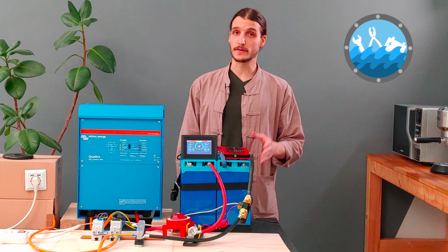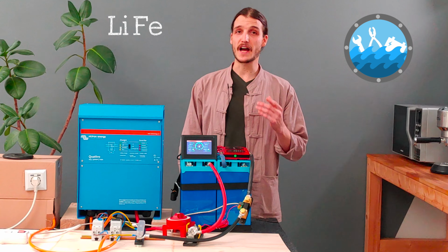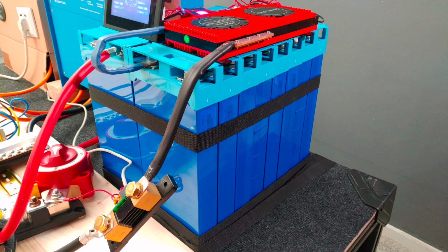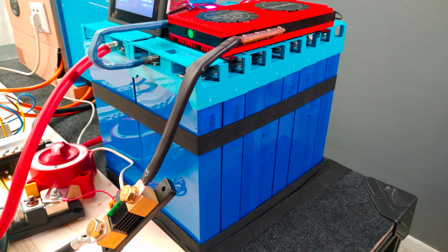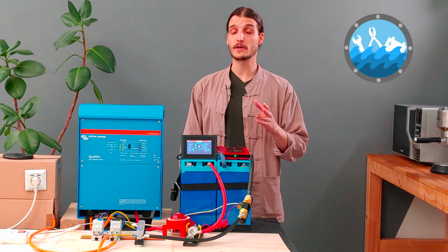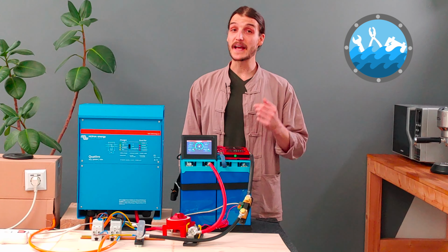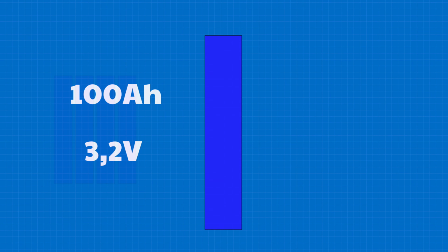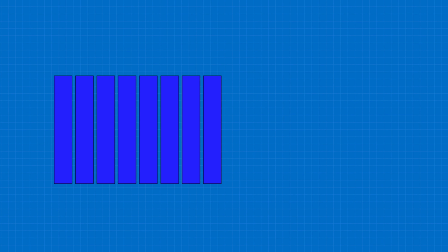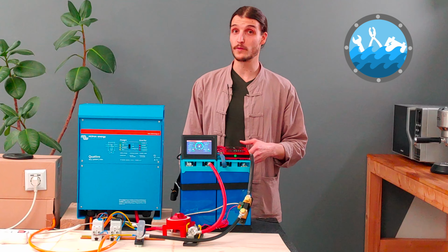Now first about this battery. It's a lithium iron phosphate battery from a Chinese brand called Frey. It's set up in a 24-volt configuration with around 200 amp-hour capacity. The bank is composed of 16 individual cells with 100 amp-hour capacity and a nominal voltage of 3.2 volt each.